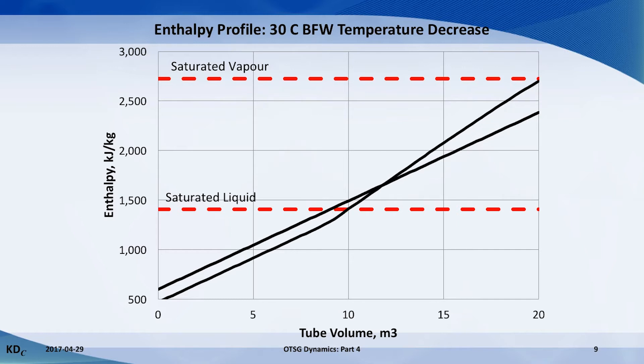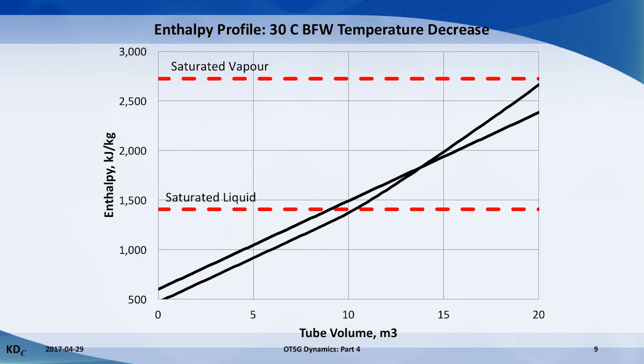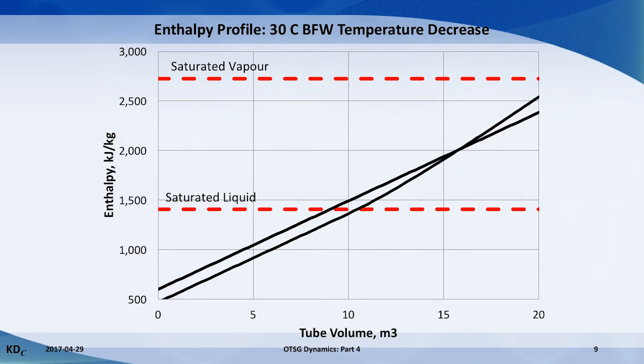The enthalpy in the radiant section increases because there is less water available to keep the radiant section cool. The steam leaving the OTSG is briefly superheated, then the enthalpy dips back down to the expected value.